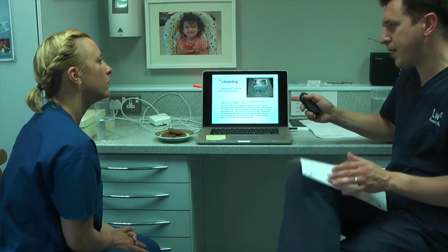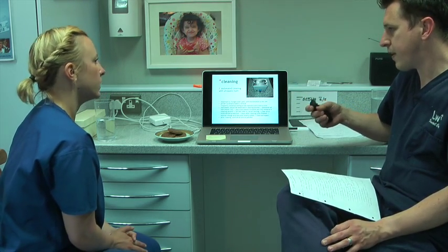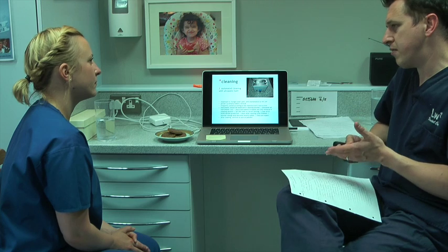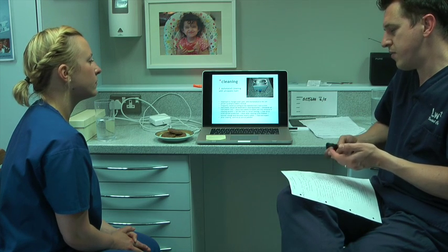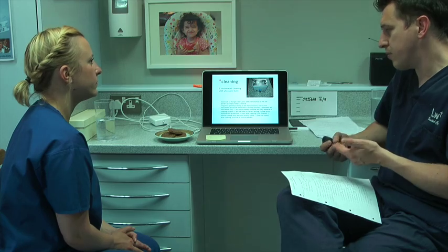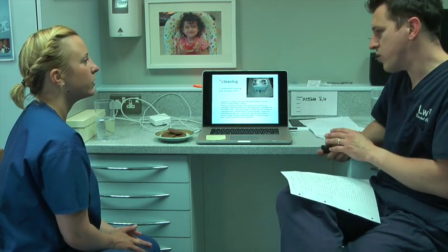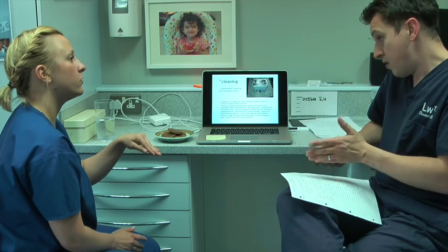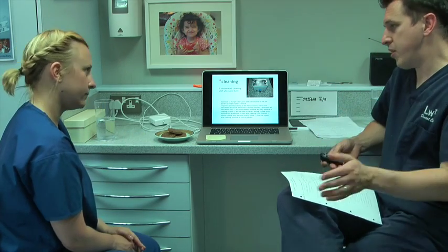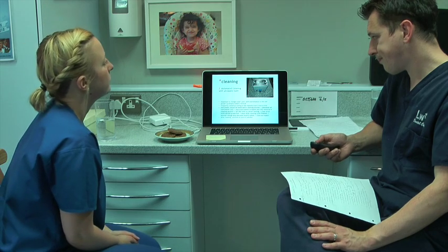The problem with ultrasonic bath cleaning is that it can take a good few minutes to clean, and if you've got material stuck on there and you've not physically scrubbed beforehand, it may not come off. So you might want to swap the manual cleaning with the ultrasonic cleaning, or it might be good to do the manual cleaning first, then rinse it, and then put it in the ultrasonic bath to agitate. That would probably be the best way to do it.